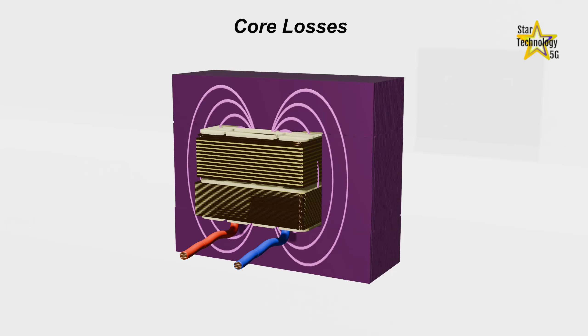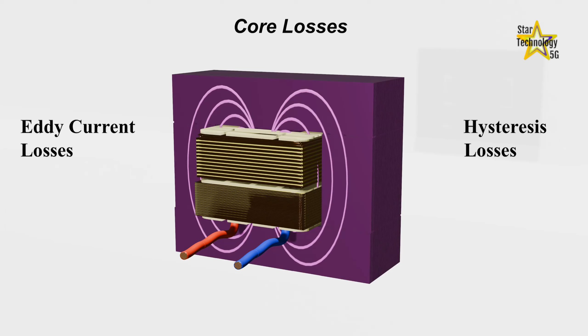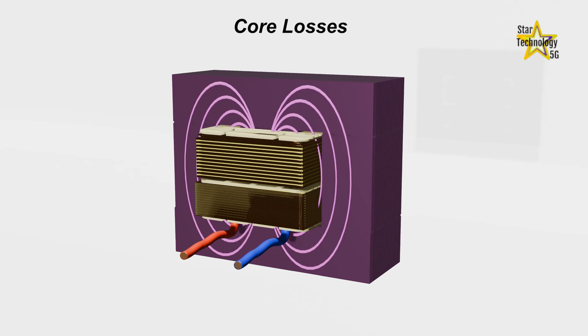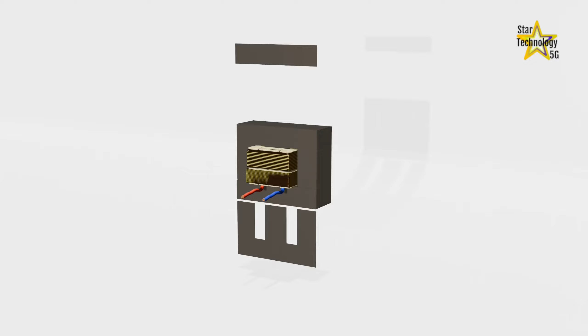Core losses. When magnetic flux flows in the steel core, losses occur in the steel. There are two components of this loss, which are termed eddy and hysteresis losses. When magnetic flux flows in the iron core, it also induces current in the core, and that current is called eddy current losses. If a solid core were used in a transformer, the losses would be very high and the temperature would be excessive. It can be controlled by reducing the thickness of the iron core steel. For this reason, sheets are cut in the shapes E and I.